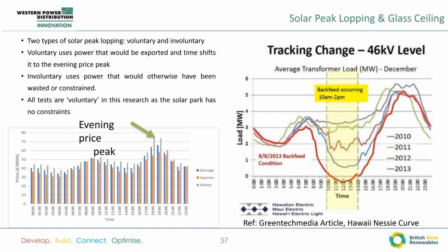But to give you an idea of why this could be helpful, if you look at the graph on the right, this is Hawaii, and there's a thing called a duck curve, which shows the push down of power prices in the summer in the UK from solar. And in Hawaii, they've got a huge amount of solar, and so they have something called the Nessie curve, which is a much steeper, much sharper curve. So they're getting backfeed. In 2013, they got backfeed at 46 kV level, so pretty high up in the network. And then they're often running oil generators, I believe.